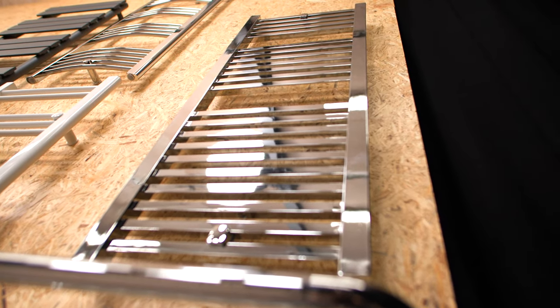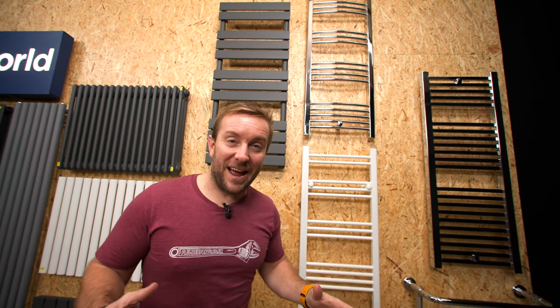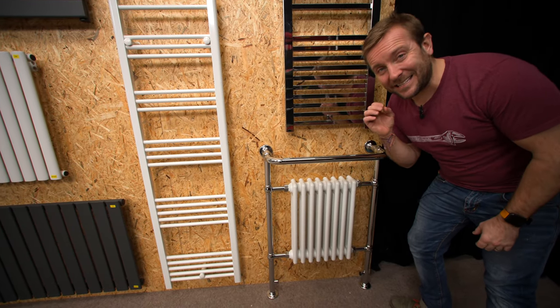But that's not really their job a lot of the time — their job is mainly to be a towel radiator. You put your wet towels on there, or when you get out of the bath, the best thing ever is getting a nice warm towel off that beautiful-looking designer radiator. As a plumber I would recommend: when choosing the size for one of these, buy the BTU — over-spec it slightly — by at least a quarter of what you can get in the room. Also consider, if you're on a first-floor bathroom, you might want to back up the heat by putting in electric underfloor tiled heating, which I've actually got in my en-suite and it works really well. Or if you're on a ground floor, you could put wet underfloor heating in. I actually fitted this exact radiator on my YouTube channel for my mother-in-law — it had to be exactly right, otherwise I'm out of the will.